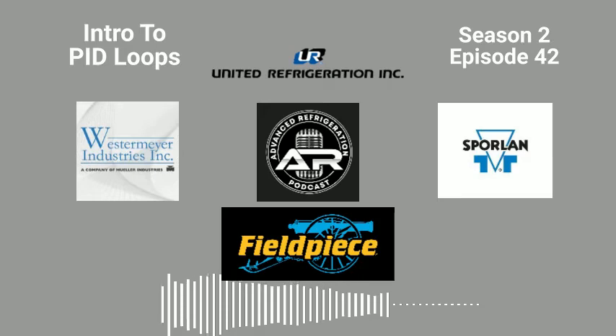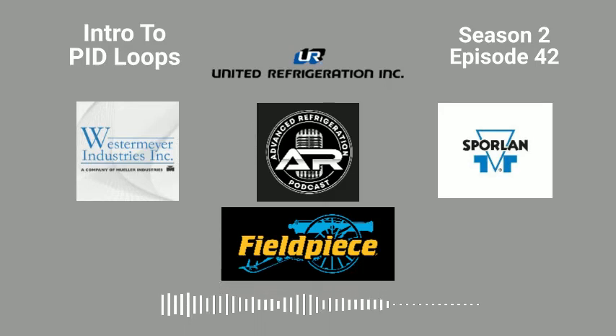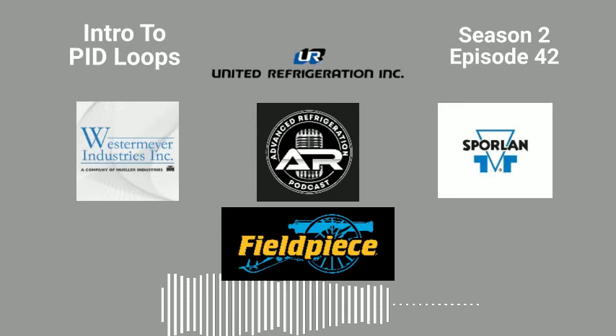The issue with Emerson stuff is the update rates. You've got to watch. A lot of Emerson stuff is 20 seconds, 2 seconds, 4 seconds. The lowest you can go on CPC is 2 seconds. A lot of other process loops run every second or every half second, like Micro Thermo, every half second to a second. That's one thing you've got to take into account, is how fast this loop is updating. Because if you're trying to update a PID loop every 20 seconds, it's not going to work. If you're trying to do a control algorithm and you're updating it every 20 seconds, you're just fighting yourself.